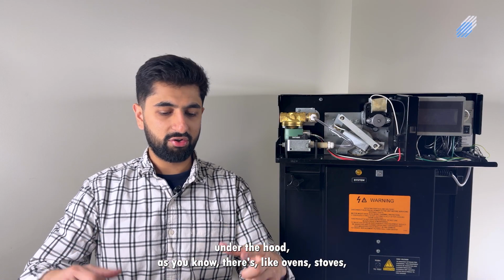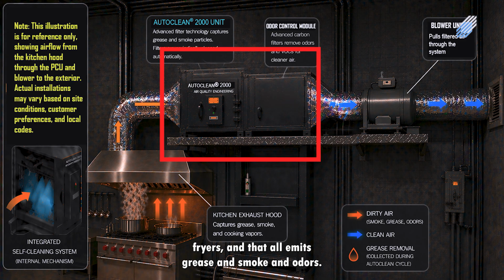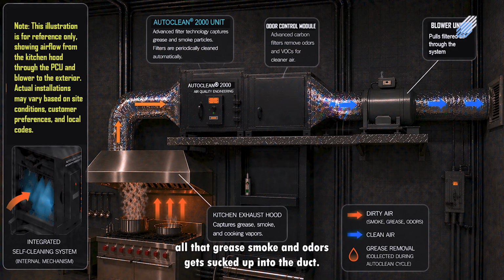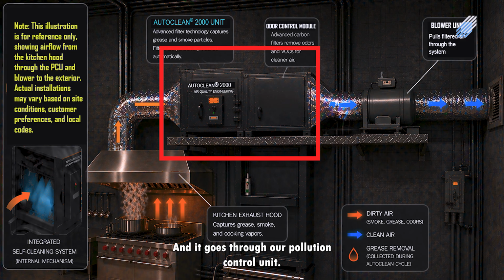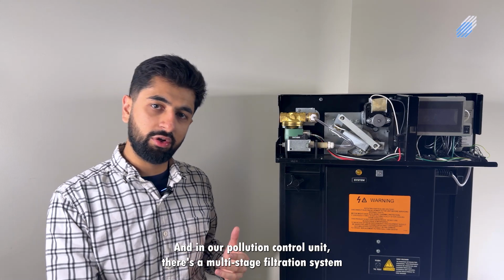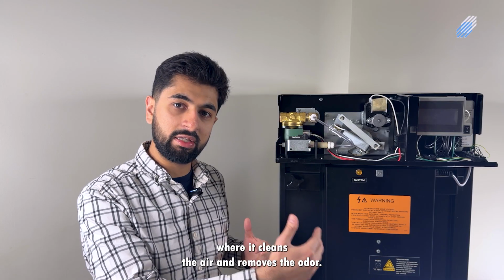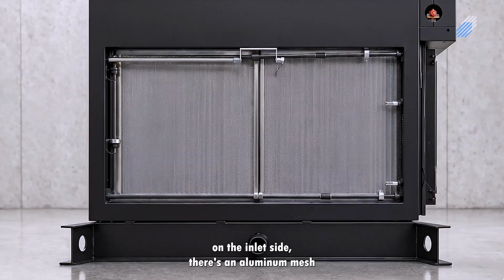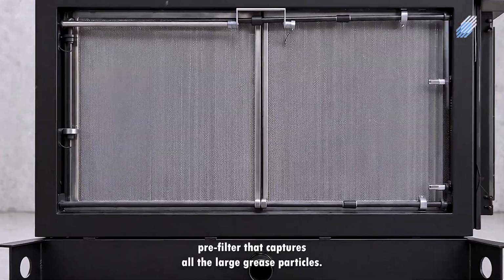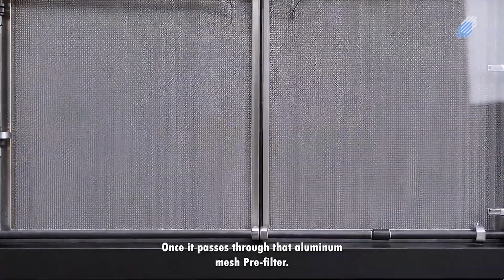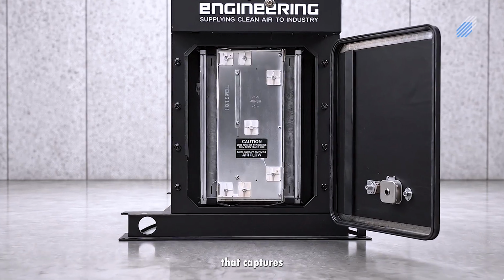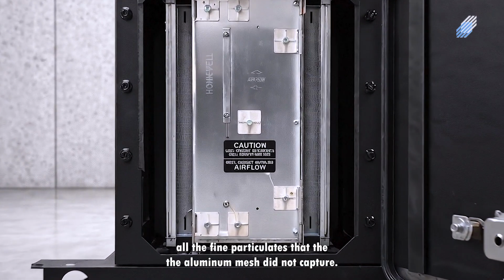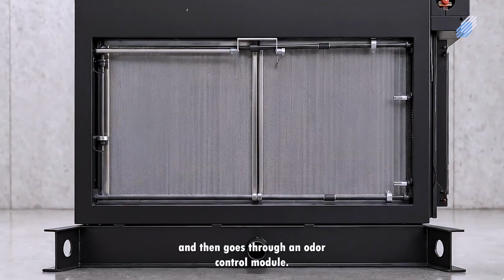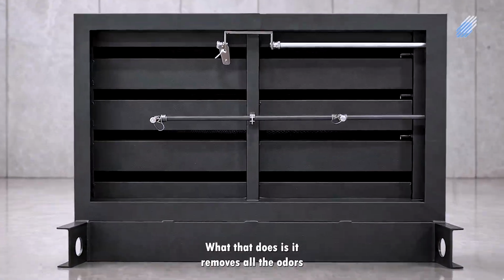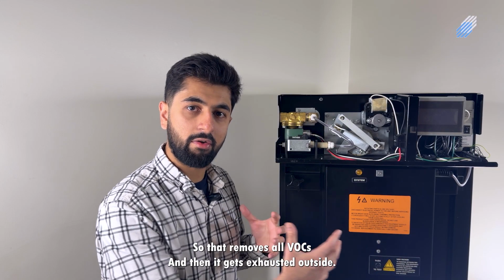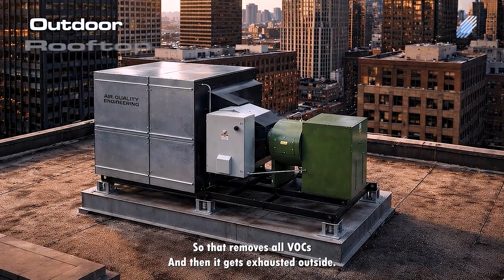Under the hood, as you know, there are ovens, stoves, and fryers, and all of that emits grease, smoke, and odors. All that grease, smoke, and odor gets sucked up into the duct and goes through our pollution control unit. In our pollution control unit, there's a multi-stage filtration system that cleans the air and removes the odor. On the inlet side, there's an aluminum mesh pre-filter that captures all the large grease particles. Once it passes through that, it goes to the electrostatic cell, which captures all the fine particulates that the aluminum mesh did not capture. Then it goes through another pre-filter, and then an odor control module. What that does is remove all the odors. It's carbon filters, so that removes all the VOCs, and then it gets exhausted outside, and that's the clean air.